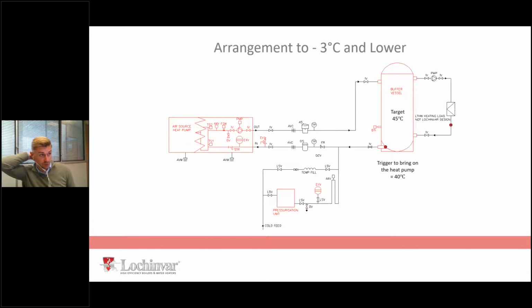That's absolutely fine, because what will happen is when it returns to the buffer, it will blend back up, because what we're doing is we're circulating faster on the primary than the secondary. So we have 2 dissimilar delta Ts, one's 5, one's broader, but it will just blend and the heat pump won't care. It will just operate quite happily and keep heating to that target temperature. So that is an example of a heating system from a dedicated air source heat pump.